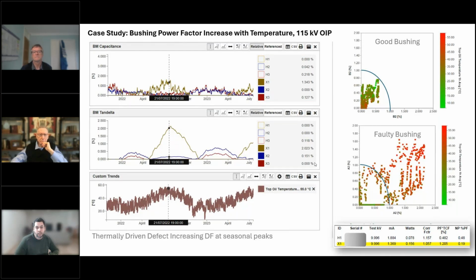If you look at the middle trend graph, labeled bushing monitoring tan delta, you see during the warmer summer months a sudden rise in tan delta on bushing X1, drawn in yellow. At the bottom there's the unit top oil temperature, and very clearly there's a relationship there. This mechanism is usually related to contaminants or moisture inside the bushing—when it migrates from the paper into the oil between the layers of the bushing insulation, it becomes actively involved in producing losses and elevated tan delta is detected. So clearly there's an understanding needed of the type of defect and what drives it.